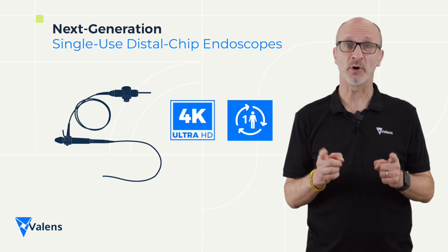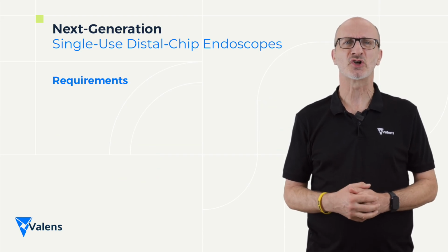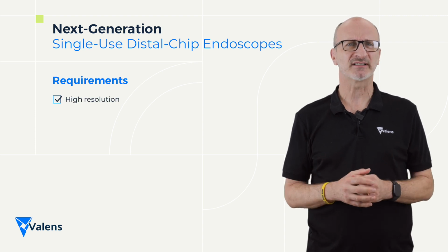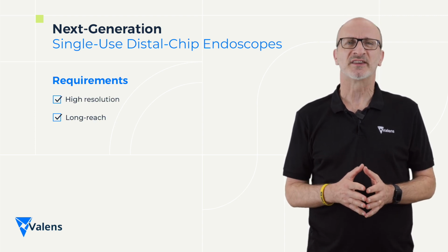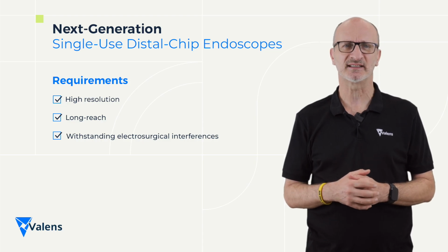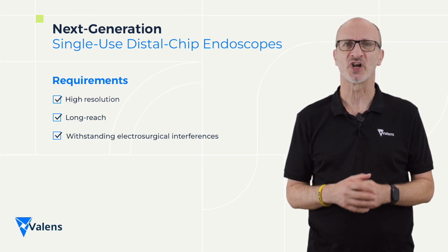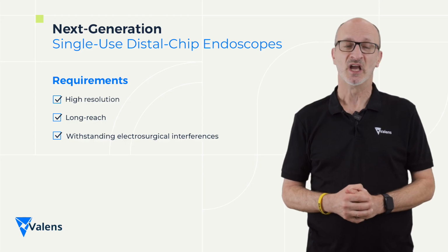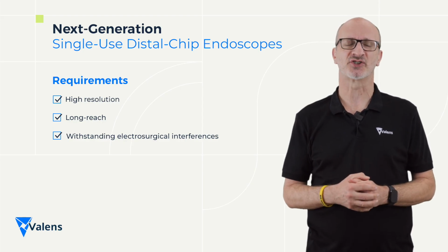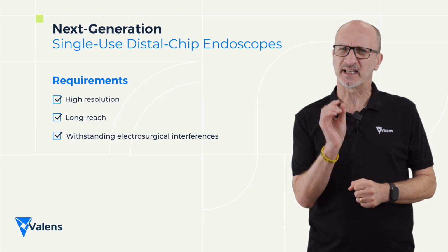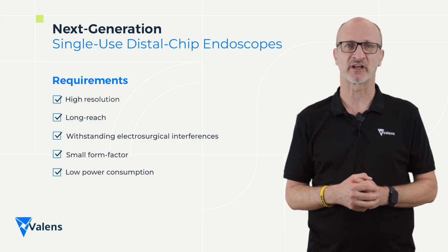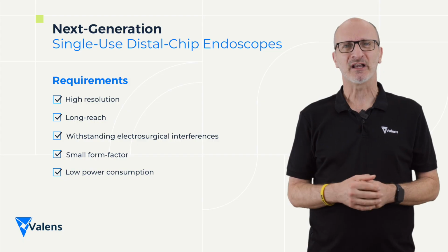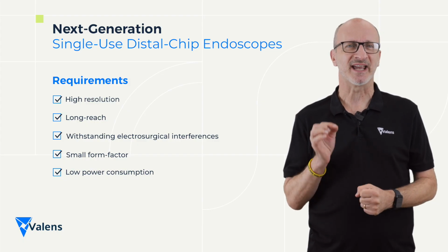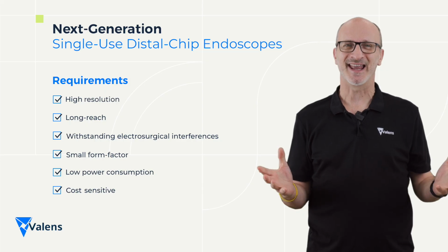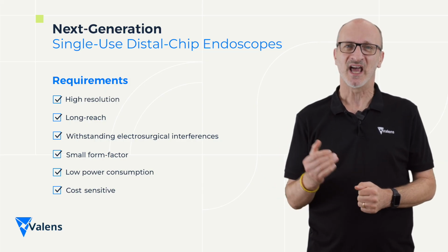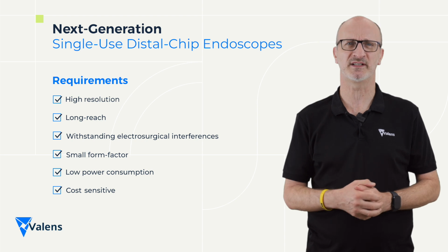In an attempt to achieve both goals, the industry has faced a technological roadblock: finding a high-resolution, long-reach connectivity solution that can withstand electrosurgical interferences without being affected and dropping the image, which can put patients at risk. To add to the signal integrity challenge, for the solution to be viable for endoscopes, a small form factor and power consumption is required. And on top of that, to be relevant for a single-use endoscope, it must be a cost-sensitive solution. Valens is excited to introduce to the market a new connectivity solution that ticks all these checkboxes.